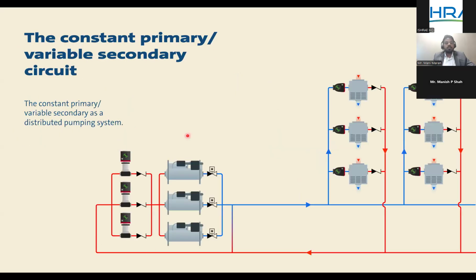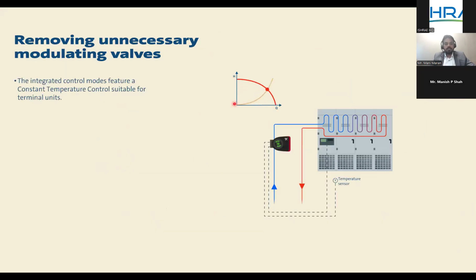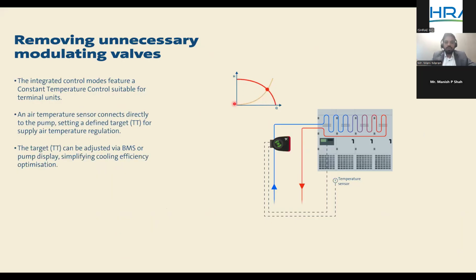So with the same primary-secondary, the primary remains the same. With the VFD, the secondary will have its own dedicated pumps connected to each coil, and the control philosophy and the design philosophy remain the same. Now, how are we controlling the flow when we have pumps across each unit? It's pretty simple. In a conventional design, the temperature feedback is given to the valve, but here the air temperature or return temperature feedback is given to the pump. The pumps, which are smart pumps today, can take analog input feedback from the temperature sensor, and we can give a set point that it has to maintain. Based on the actual feedback, the pump modulates its speed. These smart pumps, available in the market, can vary the speed as they have inbuilt drives, controls and the sensor attached to them. So based on the temperature of that unit, the flow is driven, instantly controlled by taking the temperature feedback.